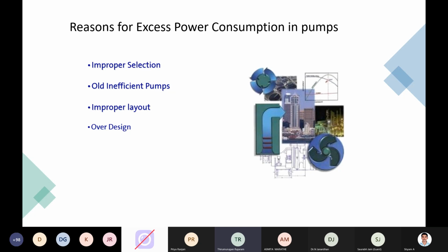Okay, and the second avenue is old inefficient pumps. We have come across pumps which have been running almost 20-30 years at site. So imagine the pumps are running. Obviously, wear and tear also needs to be considered, because such a long duration will have a lot of wear and tear, and obviously the reduction of efficiency would be immense. We have come across sites in which the initial efficiency was 80%, and over a period of time it can come down to even 50 to 40% efficiency. That depends upon the wear and tear and the condition of the pump. So for our understanding, for any pump above 7 years, we see it has almost reached 60 to 70% of its design life, you can say.